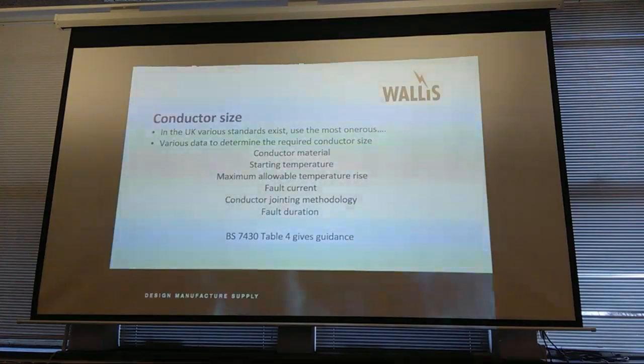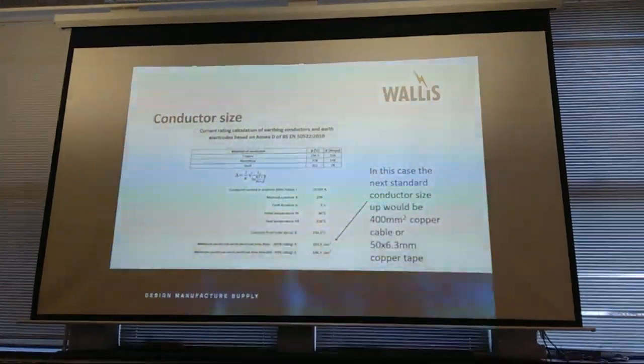And fault duration, obviously, because the longer the fault duration, the bigger the conductor you need. That is just a little takeoff, and forgive me, it was huge values because I did this for a customer out in the Middle East, but that just gives you some idea of a 31.5 kA fault current for a 3-second duration. Again, you tend to try and match the conductor size to the switchgear rating.